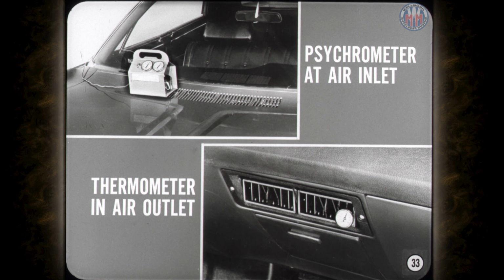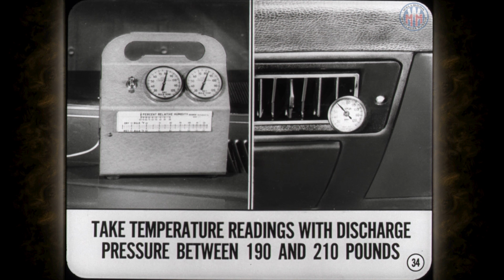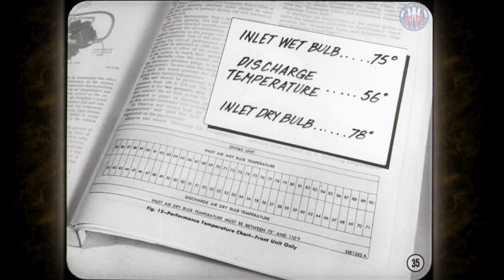Prepare the psychrometer for use and put it at the air inlet opening on the cowl. Inside the car, you insert the stem of the dial thermometer all the way into the center air outlet at the right side of the grill opening. You take the temperature readings with the system stabilized and the discharge pressure indication between 190 and 210. If the pressure is lower, you can raise it by temporarily blocking the condenser airflow. However, if the pressure is higher, cool the condenser with external floor fans. Finally, you write down the dry and wet bulb temperatures shown on the psychrometer and do the same for the dial thermometer inside the car.